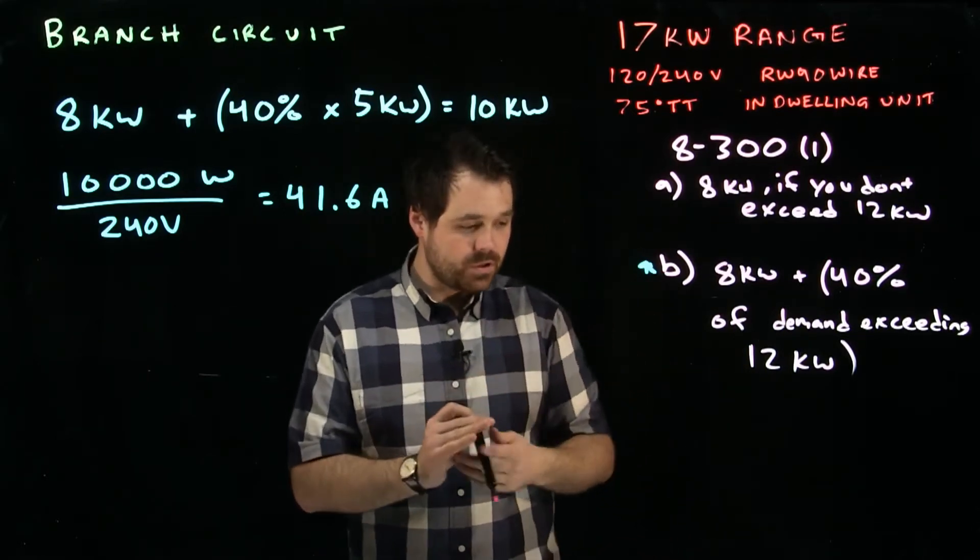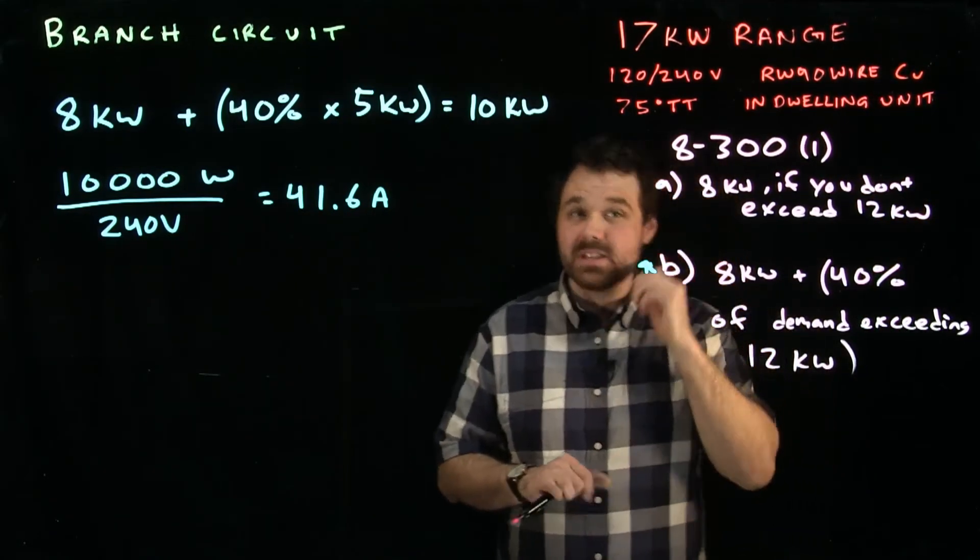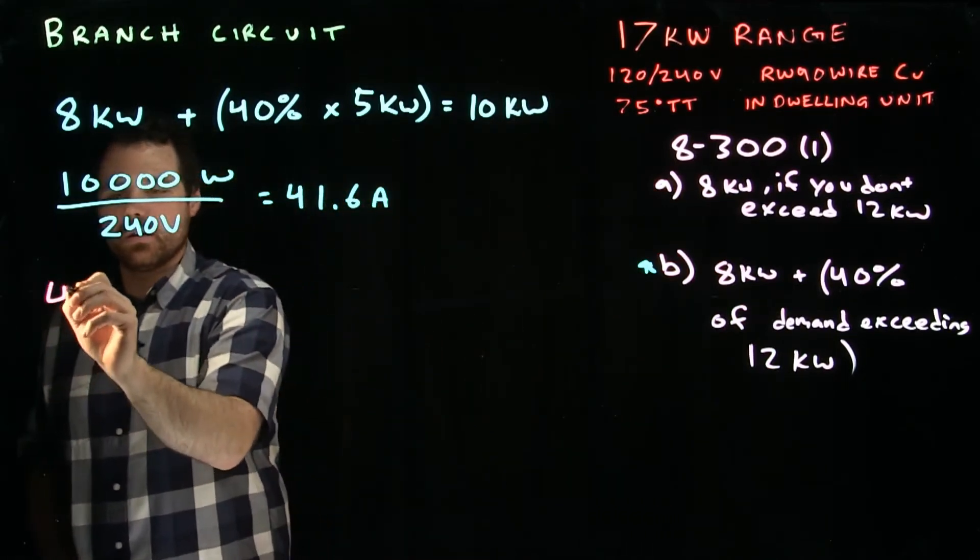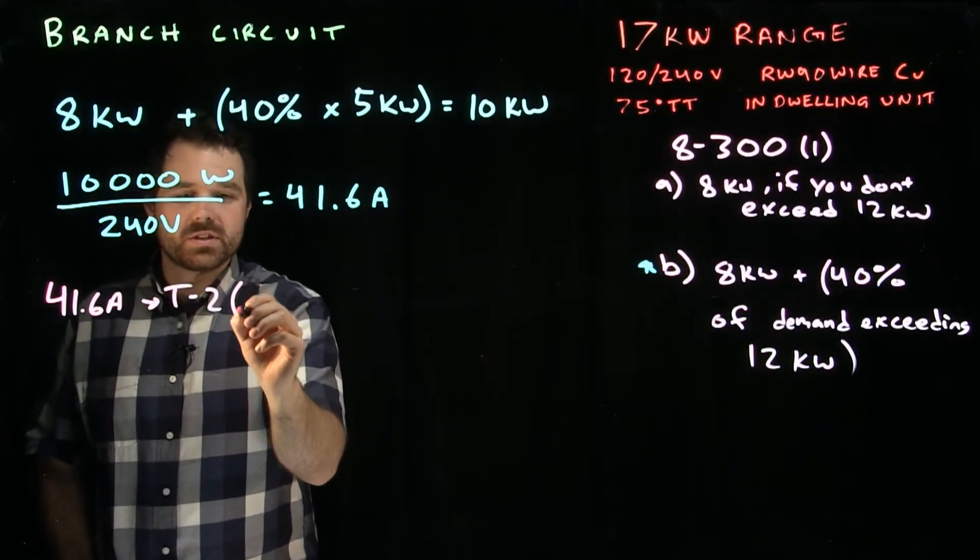With this, we're doing RW90. We'll say it is copper. RW90 copper is the conductor we are running. So we take our 41.6 amps. We're going to go to table 2.